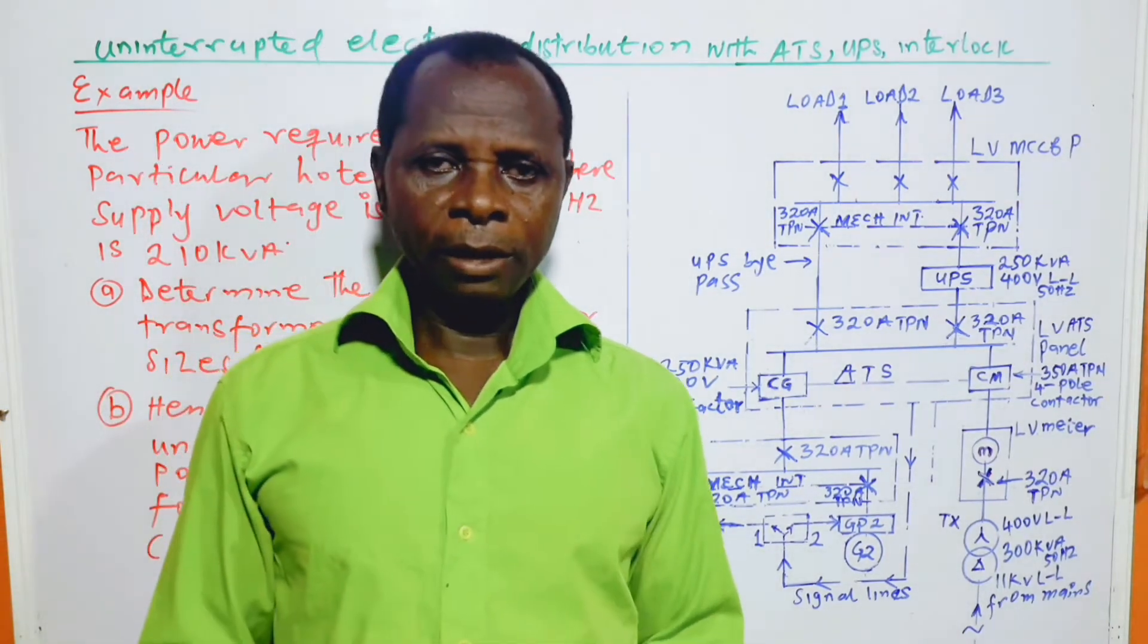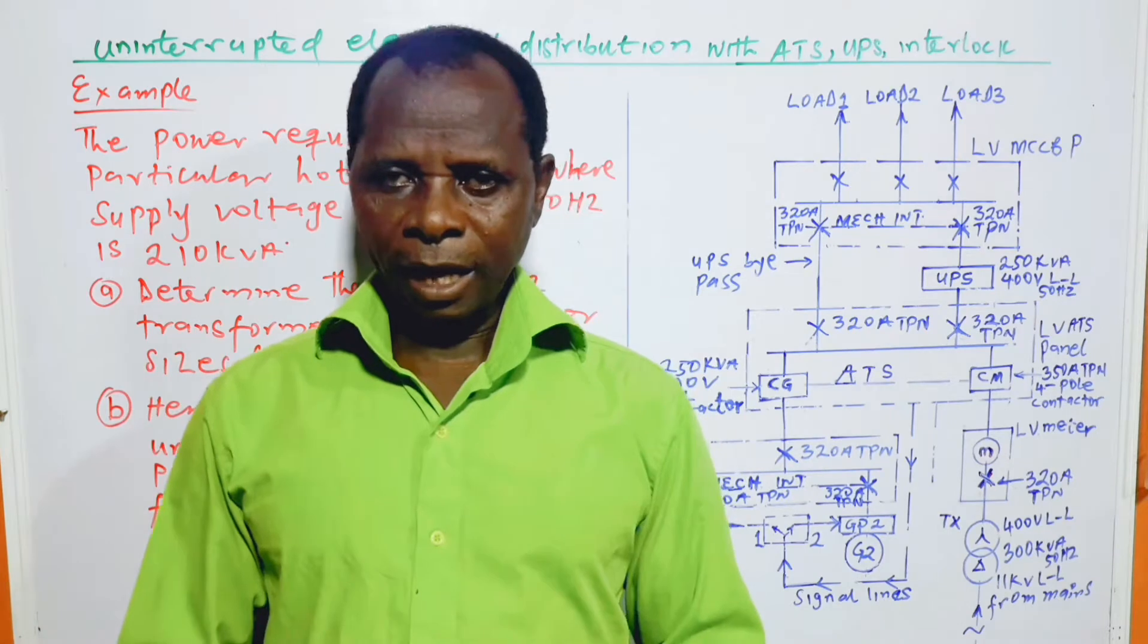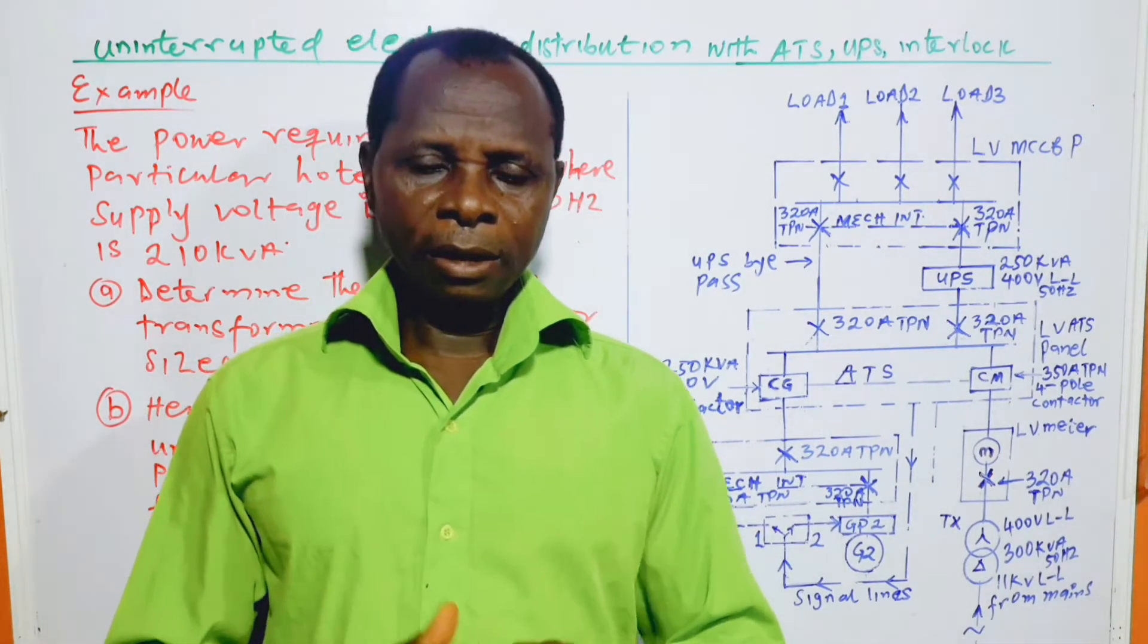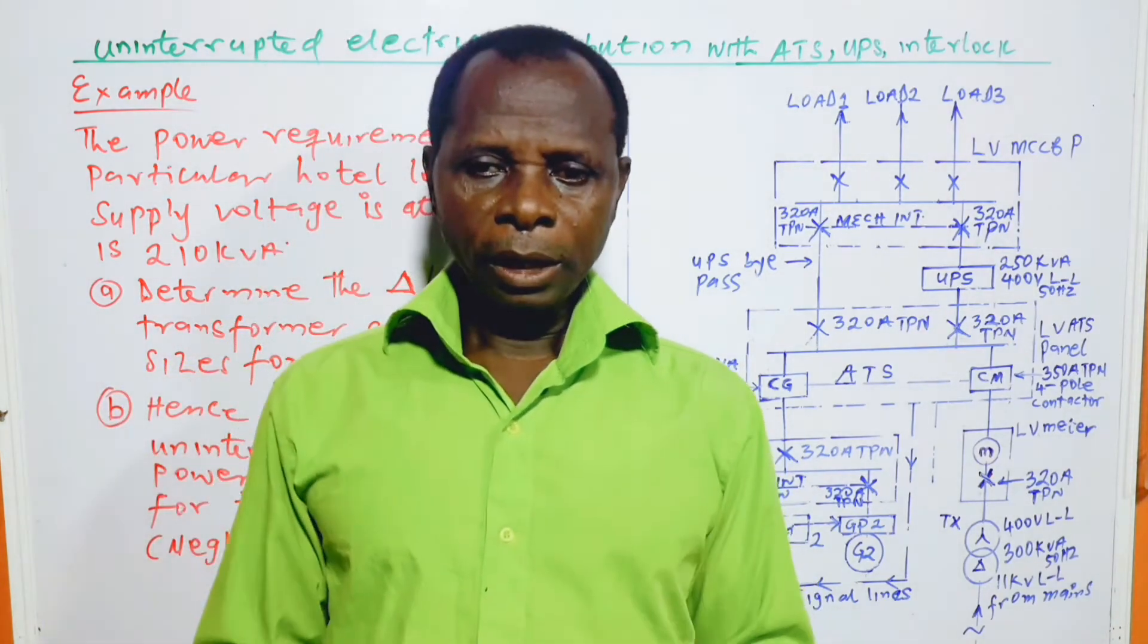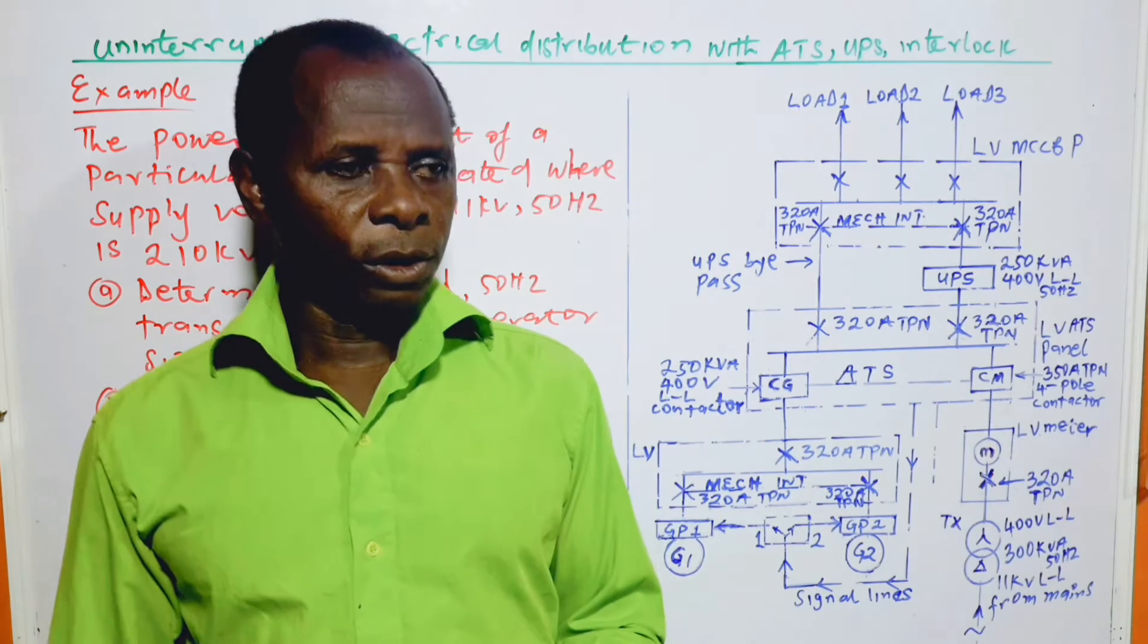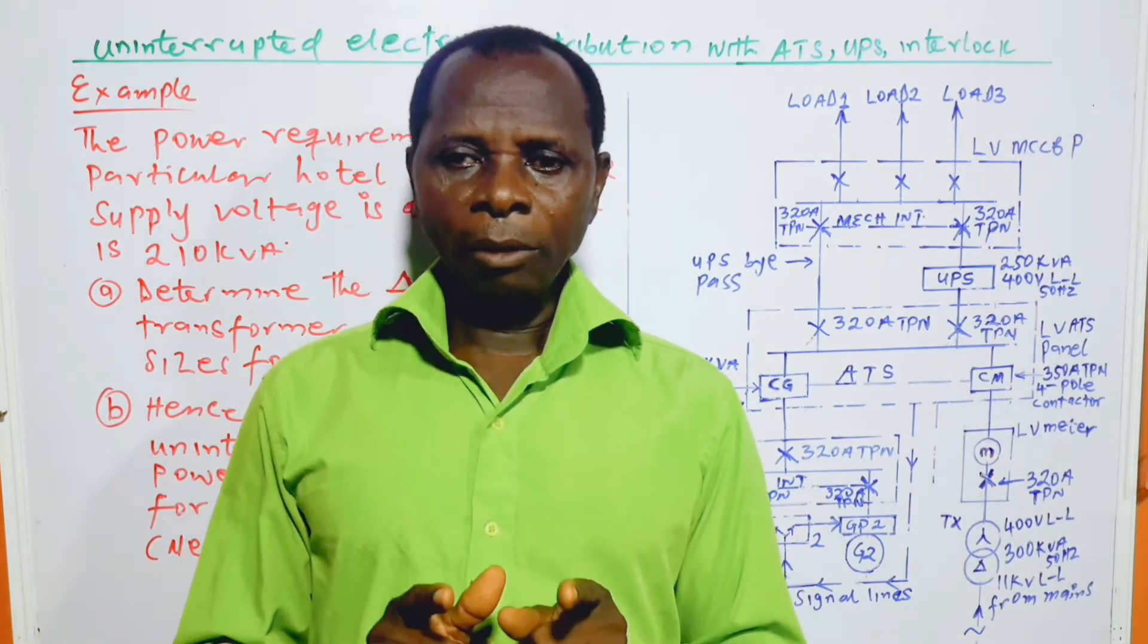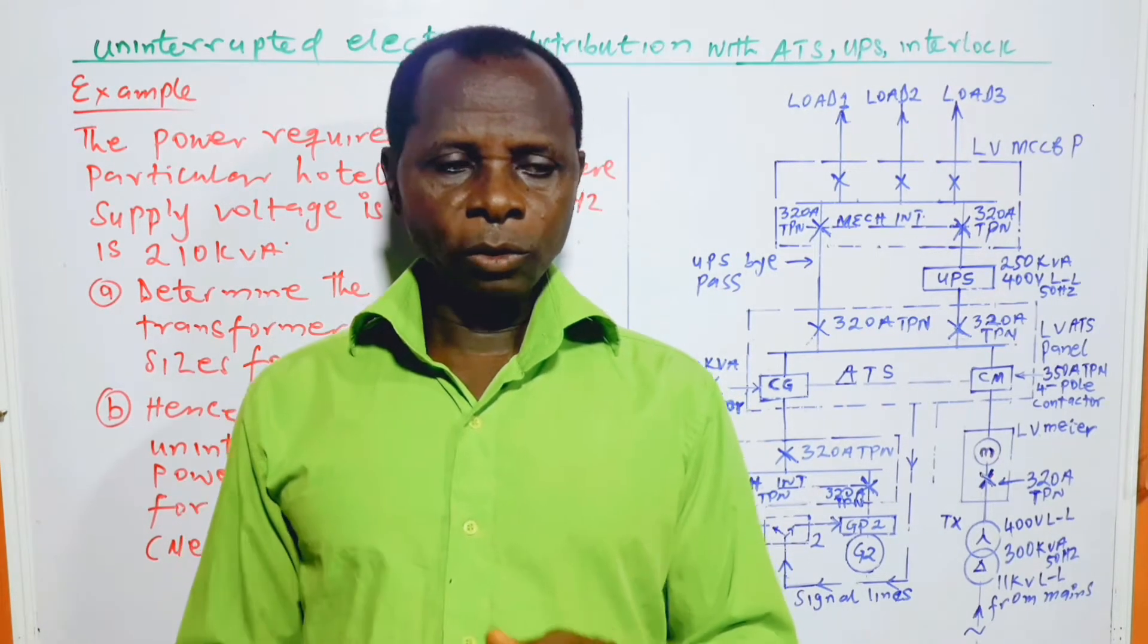Conventionally when there is a changeover from the mains power supply to the generator system or vice versa, there is always a blackout that characterizes the period of changing over. It is that blackout during the changeover system that I want to eliminate in this video. I'm going to show how a design can be done and installation can also be done to eliminate that kind of blackout. Even if it is an automatic changeover system, there is always time that is taken before the changing over is totally achieved.